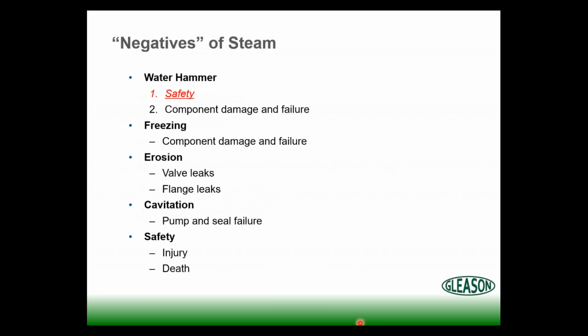Some of the perceived negatives of steam are water hammer. From a safety issue, that's something we all want to avoid. It can do a lot of damage to components. The next one is freezing. I've heard folks complain, I hate my steam coils, they freeze. Well, it's been said before that coils don't freeze. People freeze coils. And that, again, comes back to how we pipe things. We'll talk more about that.